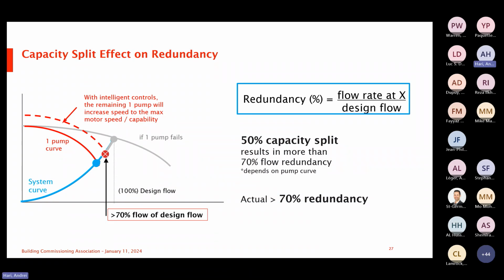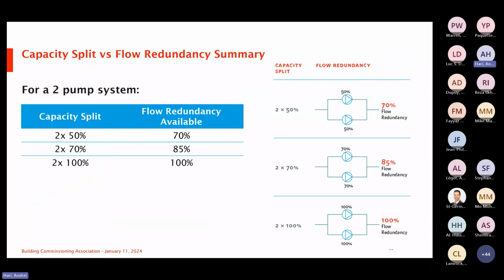A lot of times we base our redundancy on flow requirements, but our industry is moving thermal energy. So, for example, we can go to a 50% capacity split, i.e., instead of an N+1, we have 2 pumps that are half, but we are still able to meet 70% of the flow requirement and 70% of the energy movement that we require. So instead of 100% redundancy, going to 70% or 50% becomes an opportunity not only to save on the sizing and the cost of the pumps, but on the energy consumption as well.